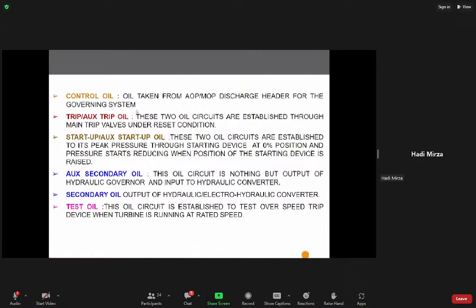Trip oil: these two circuits are established through the main trip valve under reset condition. Once the control oil passes through the main trip valve, it becomes main trip oil, and auxiliary trip oil is initiated or generated from the main trip valve. Startup oil and auxiliary startup oil are the two circuits established to their peak pressure through the starting device. When the control oil comes to the starting device, these two oils are generated, startup and auxiliary startup, which are denoted by orange color and white and orange. How it will be generated, we will see in the next slide.